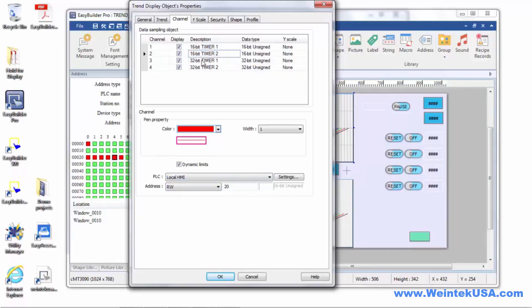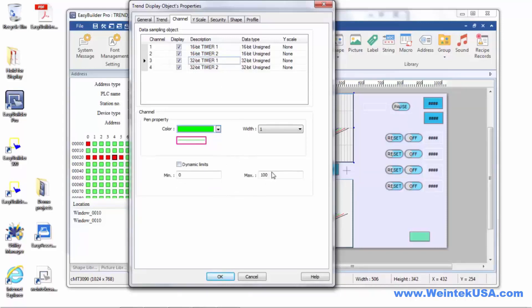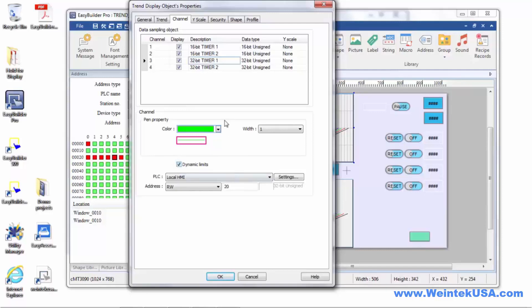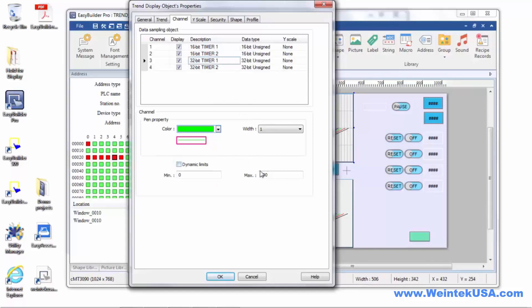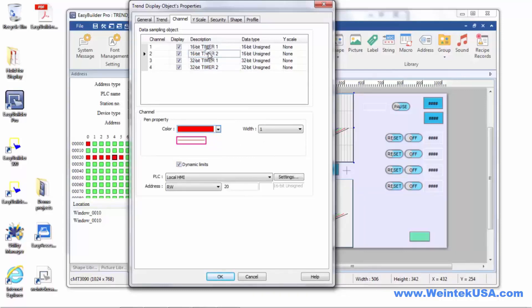If you're using dynamic limits, they need to come from a register where the limits are entered in the same data format as your display. So if we do static limits here, these limits are going to be formatted to a 32-bit format. If we did dynamic limits and read from the same register, the formatting would be all screwed up — if the value is produced by the PLC in a 16-bit format, it'll come out wrong on the 32-bit sample. So I've elected to use static limits for my 32-bit samples and dynamic limits for the 16-bit samples, which incidentally uses the same register as the preset time for all my timers.